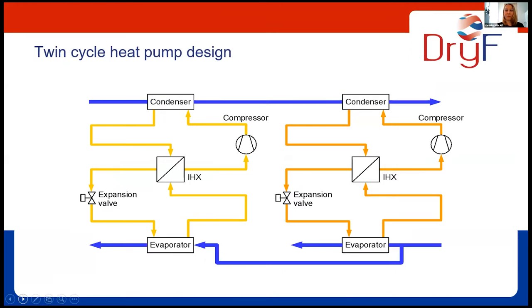This is a more technical illustration of the refrigerant cycle of the closed loop heat pump. At the beginning of the project, we carried out a large number of simulations to come up with the best suited design for the heat pump cycle. That's the twin cycle that is shown here. We have two refrigerant cycles that are connected by the water streams on the source and the sink side. The condensers of the two cycles are connected in series, and the evaporators can be connected either in series or in parallel. Here it is shown in parallel. The benefit of the twin cycle system is that one of the refrigerant cycles, shown here in yellow, is operated at a lower condensing temperature. So we get half of the heating capacity at a higher COP than the other half, which contributes to the overall efficiency.